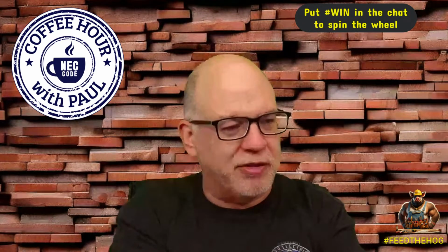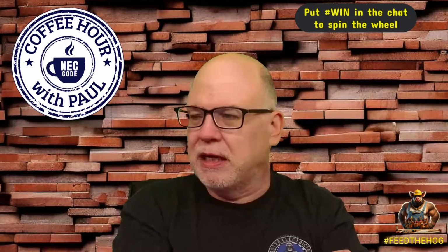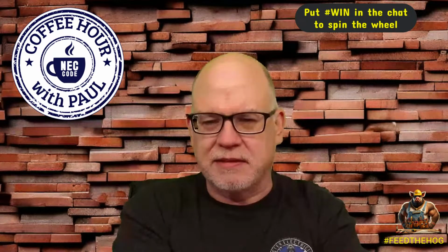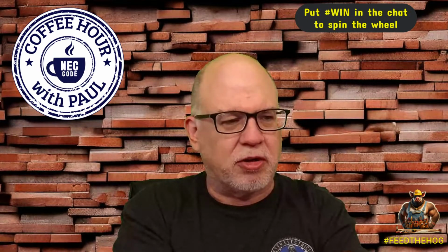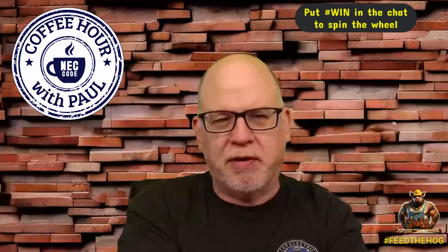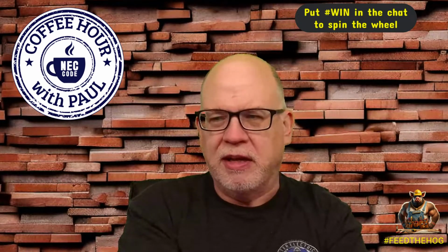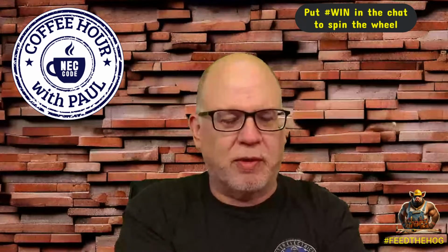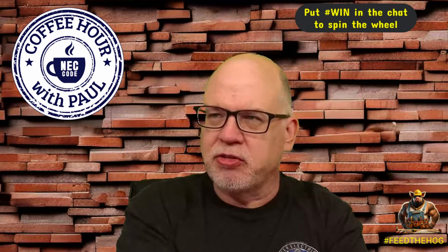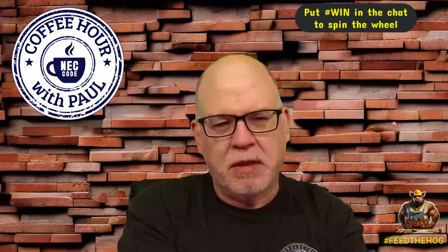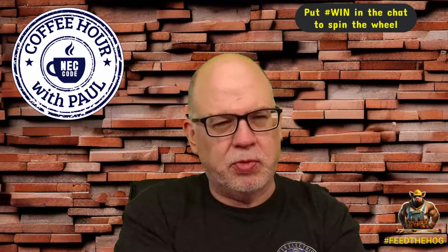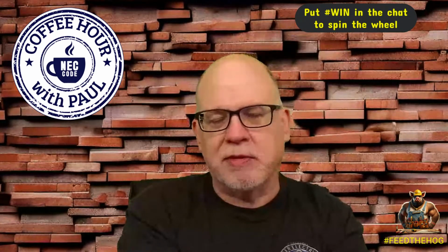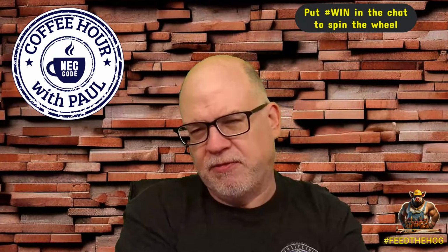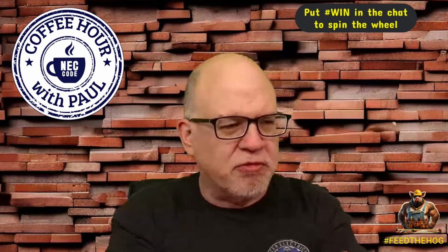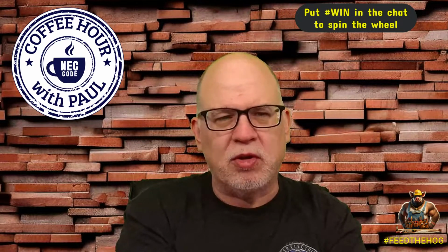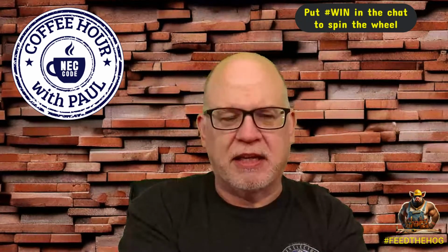Tomorrow, Friday, I will try to do something special for you. Maybe I will do the ampacities, and we'll talk a little bit about adjustment and corrections. So if you have questions, bring your questions tomorrow about adjustment and corrections. Continuous loads, 125%. We'll talk about 210.19. We'll talk about 215.2. We'll talk about the tables, 310.15(B)(11), 310.15(C). We'll kind of do a recap at the end of the week. We've probably already done this, but we'll do a little recap so that you understand ampacities.